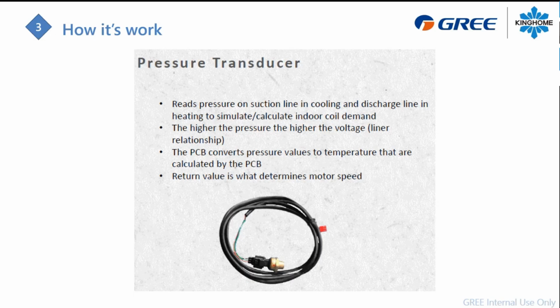If the pressure is very high or very low, the system's algorithm will manage that and drive the compressor RPM. In other words, the compressor is an inverter, so it can change its capacity. The pressure transducer here will be part of it to manage the RPM of the compressor.